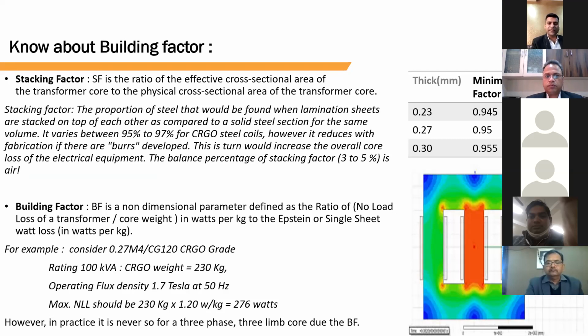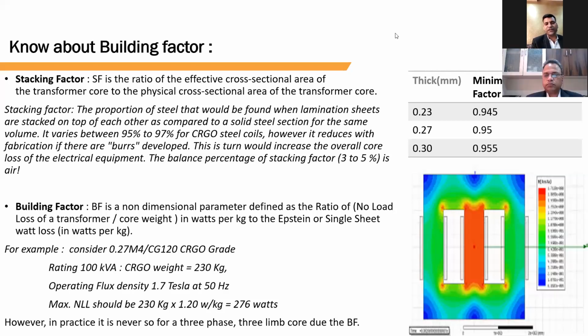In words, we can say it is the ratio of the effective cross-sectional area of the transformer core to the physical cross-sectional area of the transformer core. In simple wording, while you are stacking your cut lamination without any pressure, that is one reading, and while you are putting your lamination with a specified pressure, the difference of height is known as the stack factor. And that's why in CRGO, stacking factor varies from 95 to 97%.